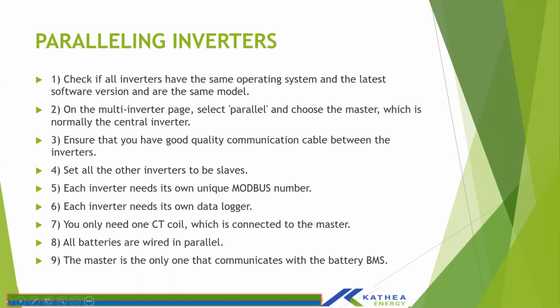And all batteries are supposed to be wired in parallel. That is the 48-volt batteries. You should maintain your battery bank at 48 volts, and all inverters should be connected to the same battery bank. You can't have each inverter with its own battery bank. So if you have 5 batteries installed in the system, you parallel all their outputs, basically you wire them to the same bus bar or line, and then all inverters in parallel simply tap on that line, such that when the batteries are empty, they'll be empty for all inverters. The moment you separate the battery banks, one inverter will still have battery while the other doesn't, especially in a three-phase scenario, and that will give a communication alarm.